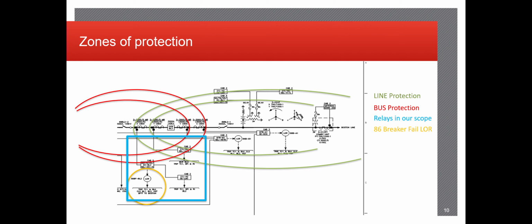And lastly, on this little string, we're going to identify the lockout relay that may be associated with the relay replacement job. A lockout relay is pretty much a device that takes in contacts from any correlating equipment, specifically the relays, for example, and operates multiple breakers all at once to cover for a worst case scenario type event, if you would. They're utilized very frequently. They're extremely important, and they can be super beneficial to mitigating a worst case scenario outage.